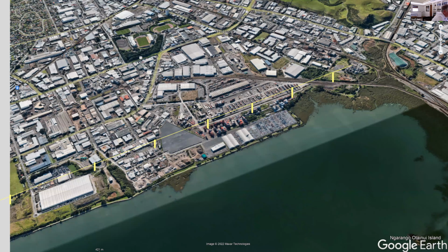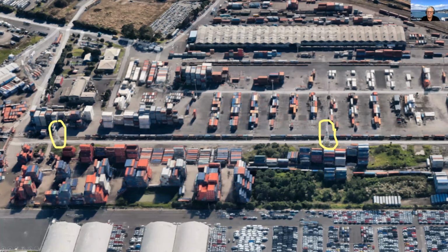On the right-hand side, where the yellow line stops, that's where the Southdown power station was - I think it was open cycle. The 220 kilovolt line ran along the water's edge through this shipping container yard. You can see the risks of a road running basically under the power line. I've highlighted the masts here, and this road going across. So anything running under this line would pose a risk to the line above, and with these containers stacked high, forklift lifts do have a reach that high.